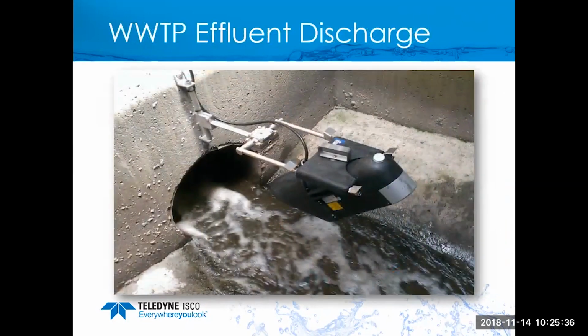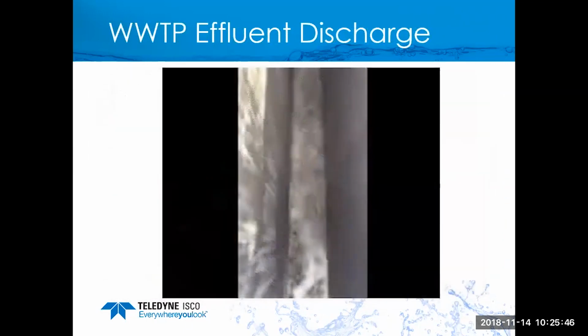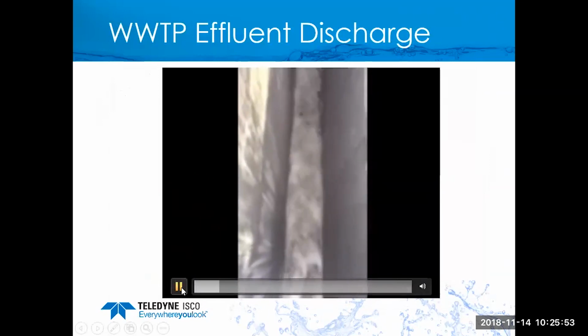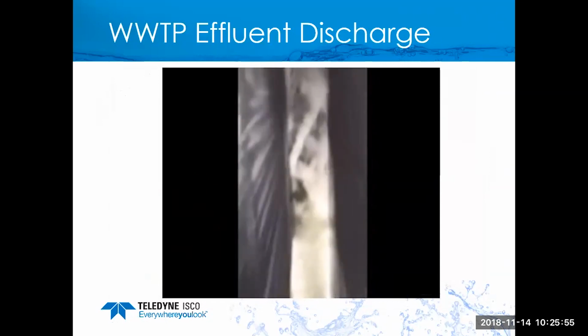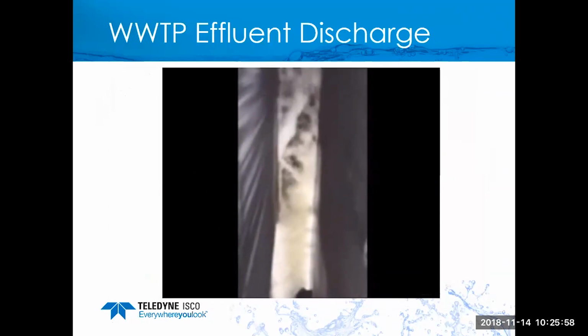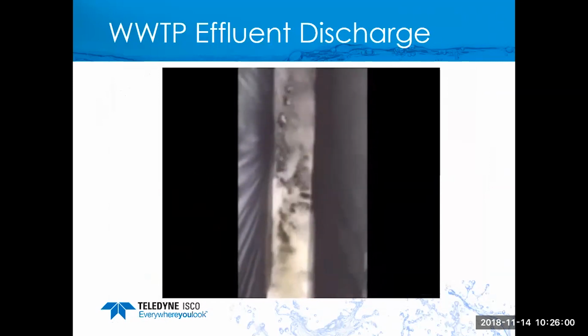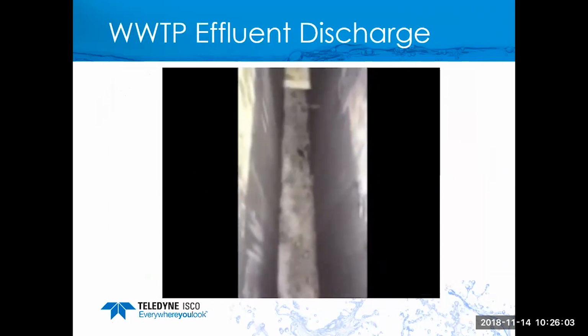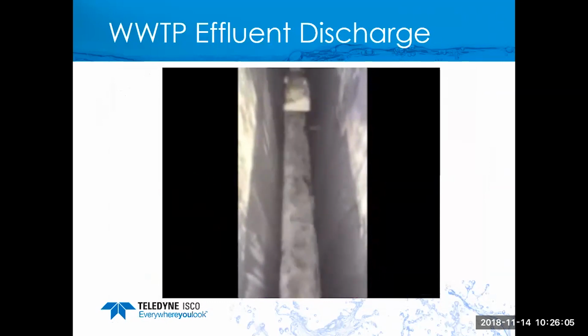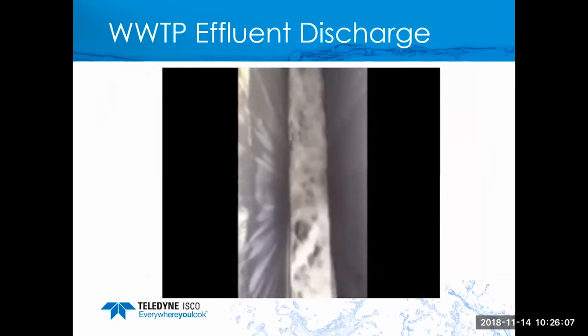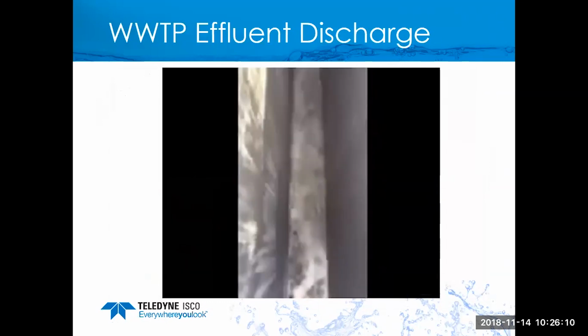Wastewater treatment plant effluent. So here's another one. A little bit of foam on this one, but the laser can handle quite a bit of bad conditions, and I'll show you one here in a minute. This is one that I have a video on. They're trying to measure this one. This is effluent of a wastewater plant. That's a 2-foot wide rectangular channel. Water's dumping into it, and then it flows down that, and you can see how turbulent the flow is, and you can see also the amount of foam in that line. So not an easy place to measure.